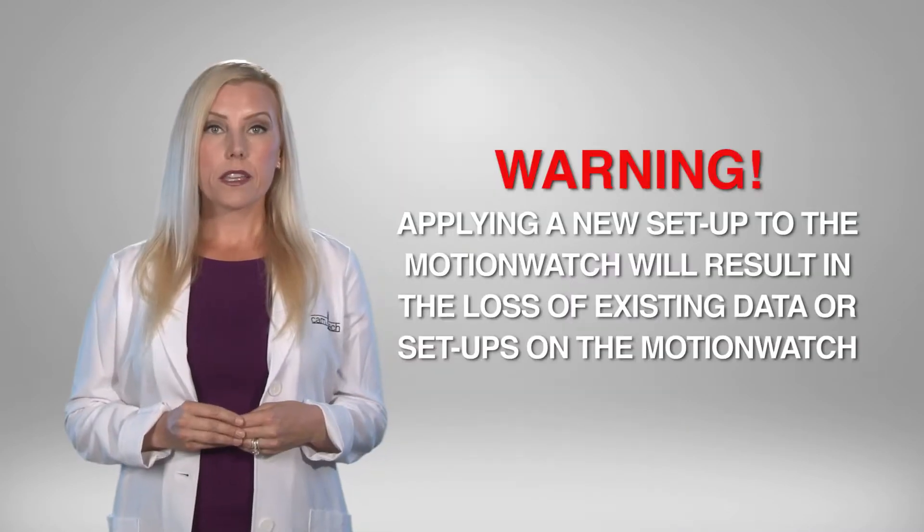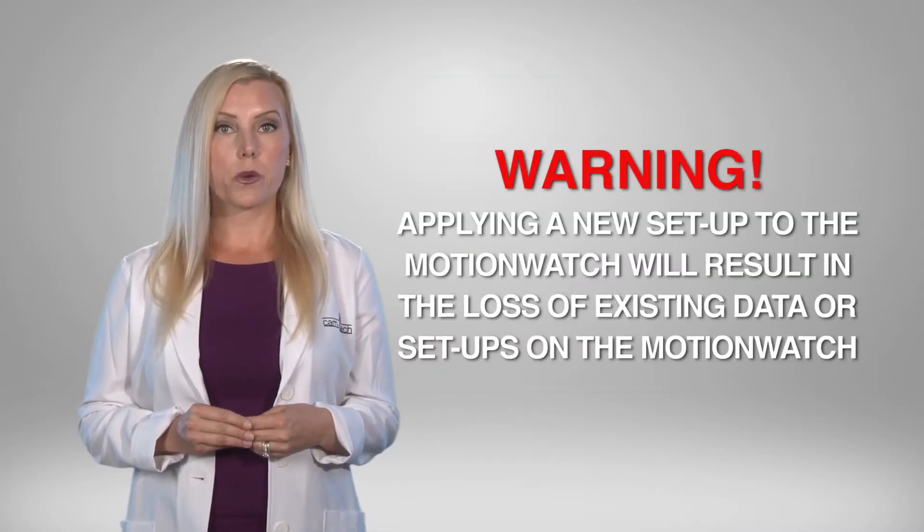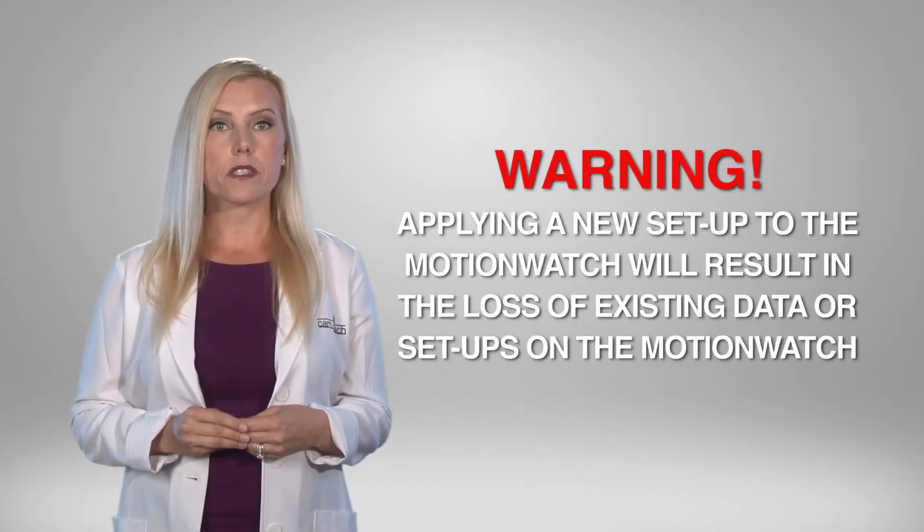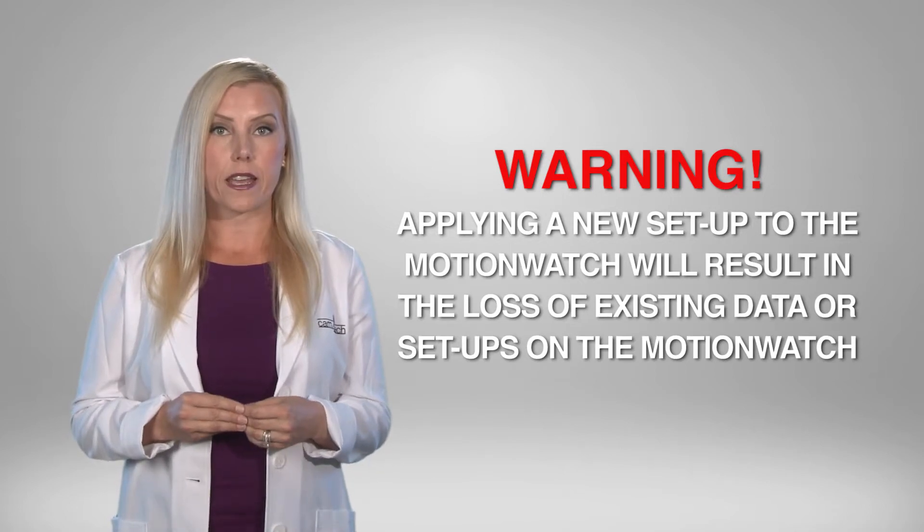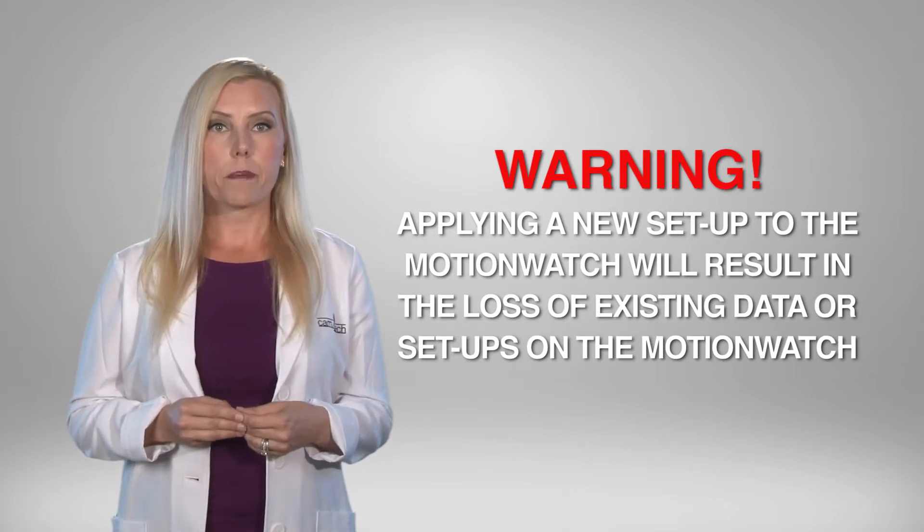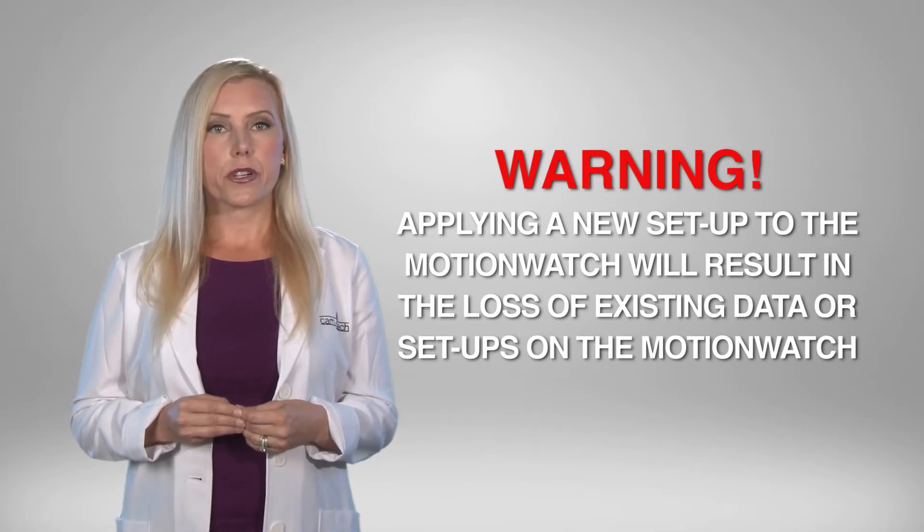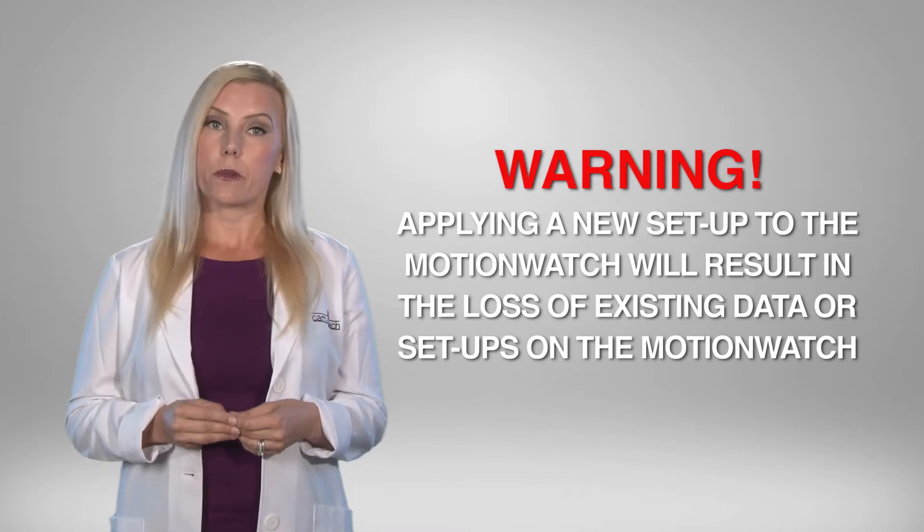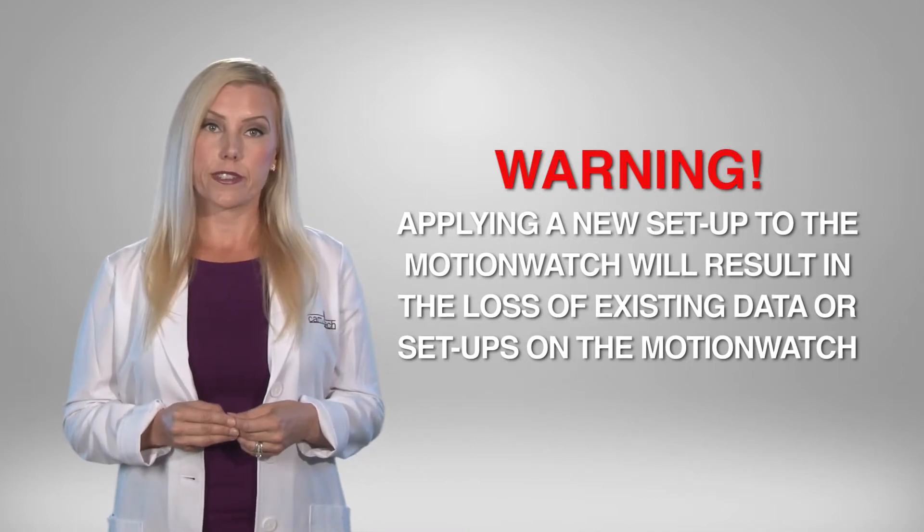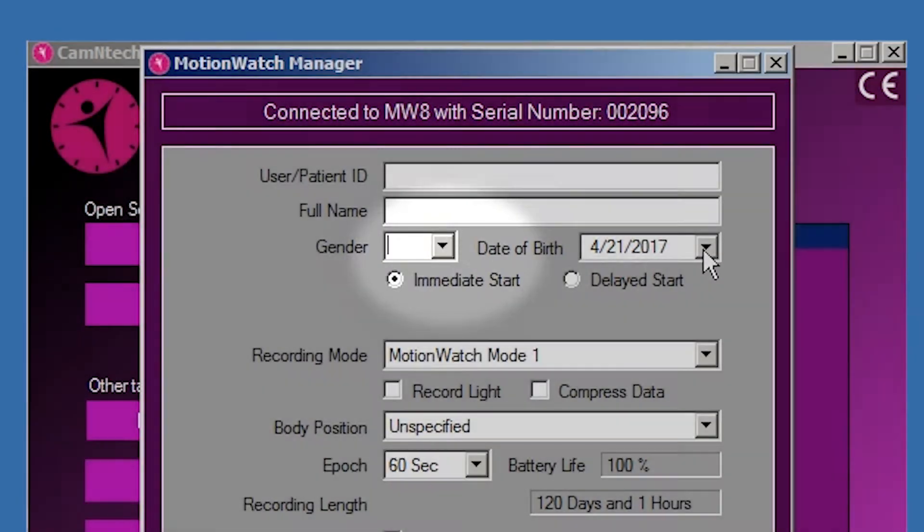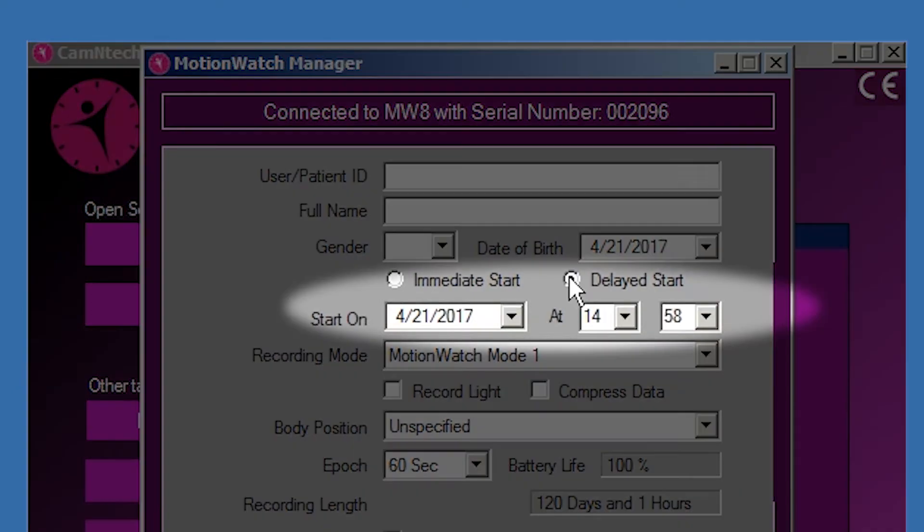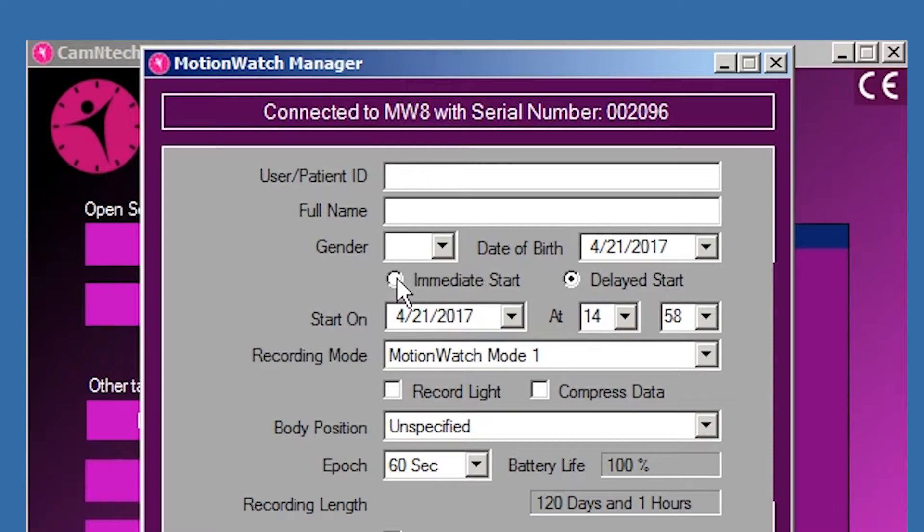Applying a new setup to the Motionwatch will result in the loss of any existing stored data or setup information. Please ensure that any stored data has been downloaded first. The Motionwatch 8 can start immediately or be set to start at a future date. Select Immediate Start to ensure that the Motionwatch begins recording when disconnected.